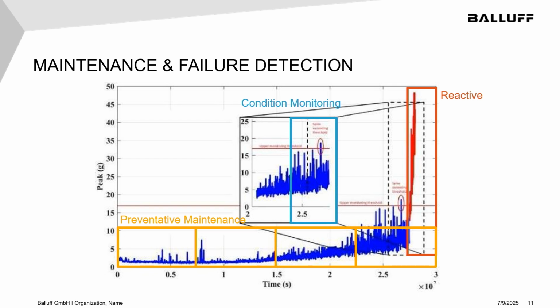Condition-based monitoring starts to look at the data coming off that machine. In this case, we're looking at vibration data. We've set a limit, and once the vibration exceeds that limit, we send an alarm to the operator and to the maintenance team to say that there's something happening in that asset and that it needs to be addressed. In this case, we set our alarms so that the vibration hit a certain level about a week or 2 weeks before the catastrophic failure would have occurred. And so we did have some warning and some time to address that failure. Relatively short time, but we did have some time.